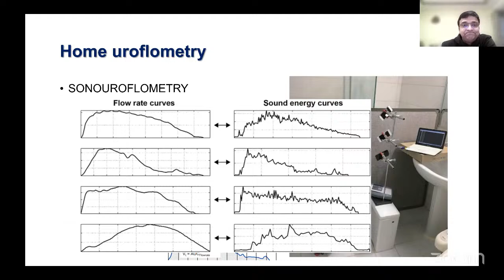Now coming to office uroflowmetry. In office uroflowmetry, the International Continence Society has laid down some guidelines about the machine which you should buy. It should be able to measure uroflow from 0 to 50 ml per second at least. It should be able to measure volume up to 1000 ml. The time constant should be less than 1 second, and it should measure at an accuracy of 5% or better. Meaning if the flow is 20, showing 20, up to 21 actual flow is acceptable.